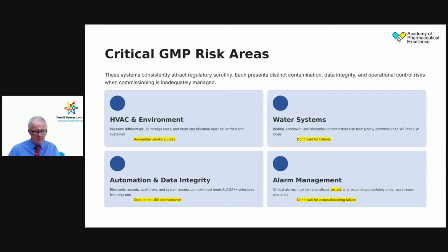Water systems are high risk. Biofilms, endotoxin, microbial contamination risk from poorly commissioned WFI and purified water. You can't wait for the failures. Make sure you've engineered out dead legs, make sure you don't have unnecessary loops, and make sure the loop they've manufactured has been cleaned.